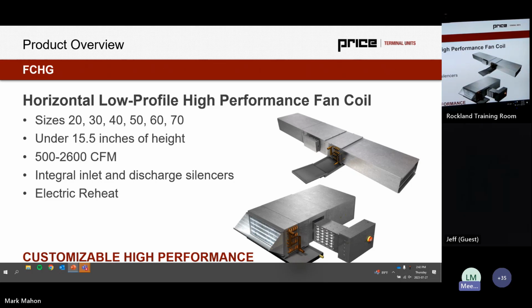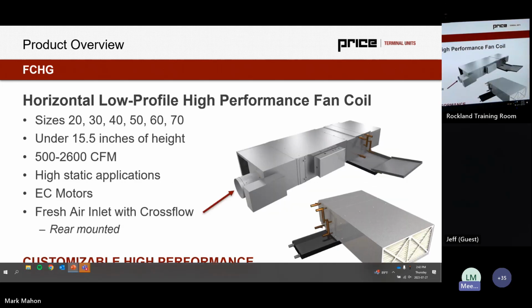So this is a product that fits a nice niche in the market. Generally, I see it specified and laid out up to about 2,000 CFM for acoustical purposes, because it's often used in acoustically considerate environments that have a shorter plenum height. It is 15.5 inches, so it's not a traditional height fan coil, but not a low profile fan coil. It sits in between. And it has a lot of options. It does come with a fresh air inlet, which is rear mounted in a mixing box. That's really a big benefit for these DOAS systems we're talking about. It comes with 2-inch thick MERV 13 filters, and it comes in a number of sizes to deliver whatever the CFM is required for the zone.